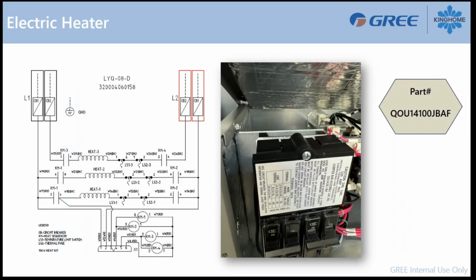For installation with a 15 kilowatt and more, using 2 breakers. Now you can see here on the schematic, this is a 15 kilowatt schematic. Same pattern, okay? Much more sequencers in that case. So 3 sets of sequencers on each side for your L1, L2, so you have circuit breaker 1, circuit breaker 2. And now to help you guys to do the connection, if it's a retrofit, you have 2 different options here. From the electric panel, you can have 2 different power lines. So in that case, for a 15 kilowatt, we are using a 30 amp breaker and a 60 amp breaker. So you can have from the panel 2 different power source breakers, so a 30 and a 60 amp.